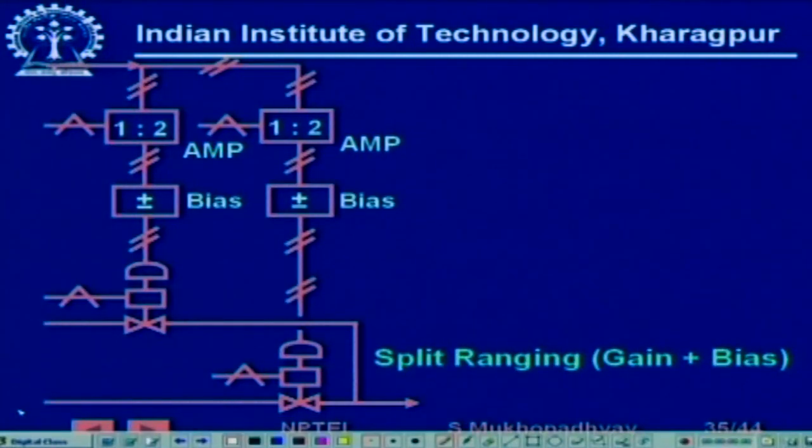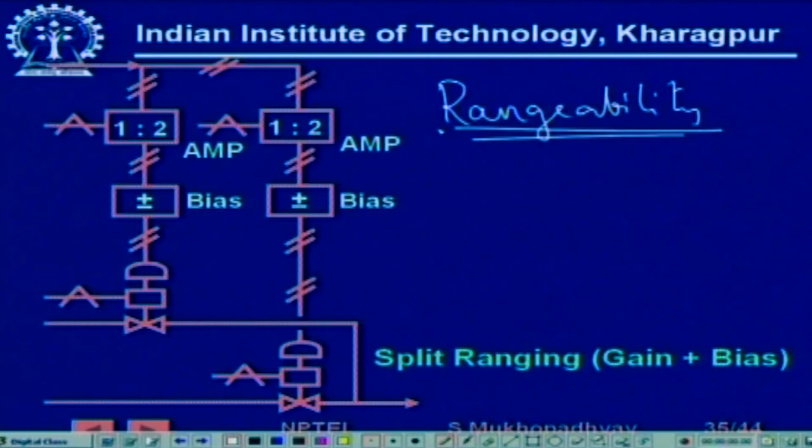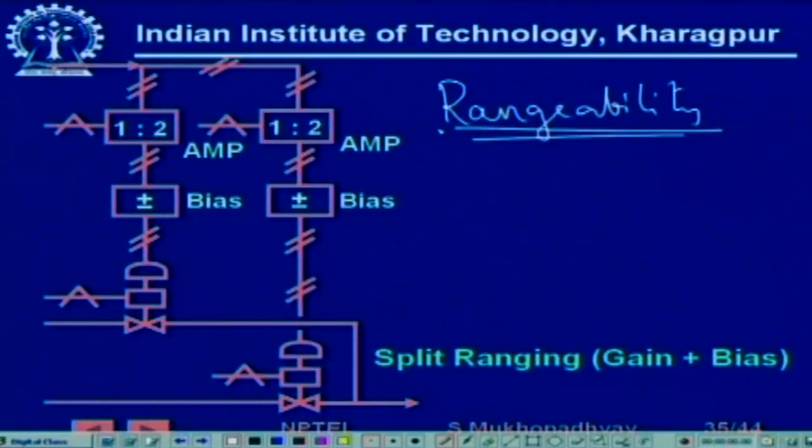Similarly, there is a very important quantity for a valve called rangeability. Rangeability means the maximum to minimum flow ratio, that is, the maximum flow to the minimum controllable flow. Valve manufacturers sometimes claim 10:1, 15:1, 30:1 rangeabilities. In some applications you need a very high rangeability, that is, sometimes you need very, very small flows and sometimes very, very high flows.